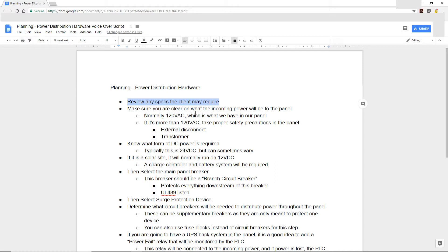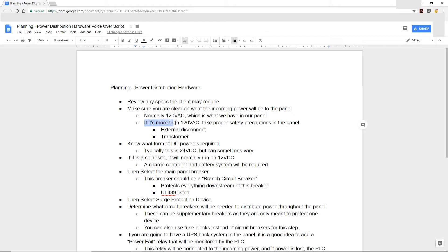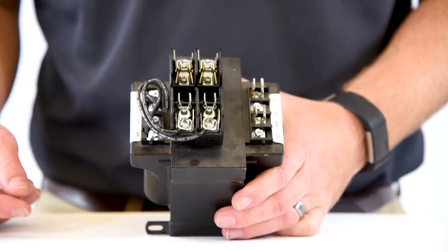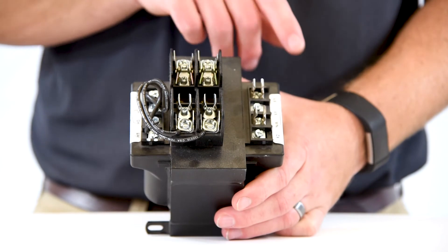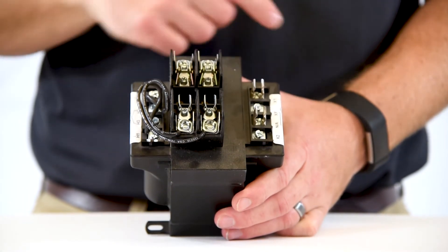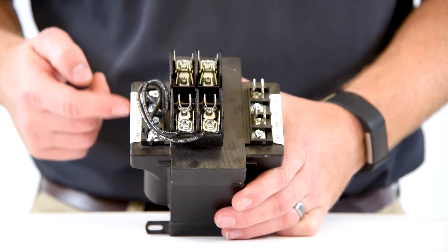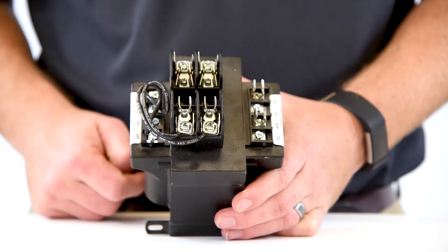We're going to review the specs for our power distribution hardware to make sure the hardware we're selecting meets any requirements. The next thing we want to do is be very clear on what the incoming power will be to our panel. Normally in a control panel such as the one we build, we typically see 120 volts AC, which is what we'll have in this particular case. But sometimes we do see more than 120 volts — if we happen to see 480 volts three-phase, we need to make sure we take proper safety precautions, which may mean putting in an external disconnect, a transformer to reduce that voltage down to something more manageable, and other necessary safety precautions.